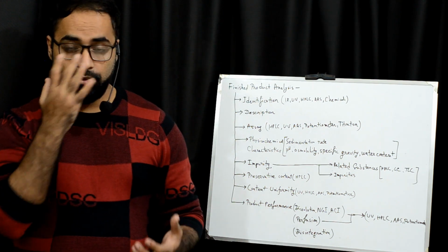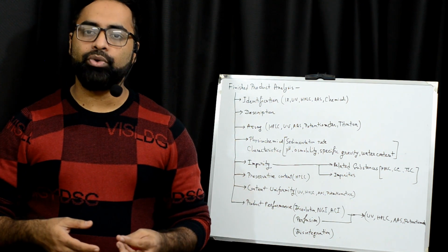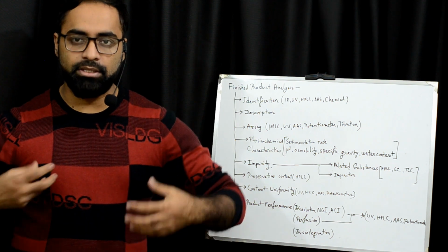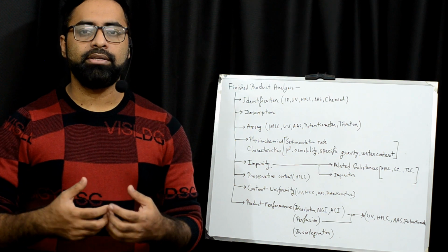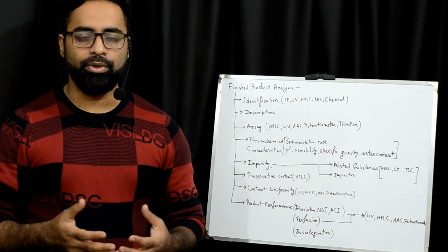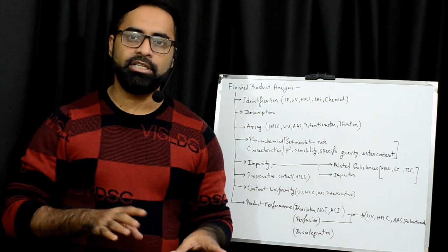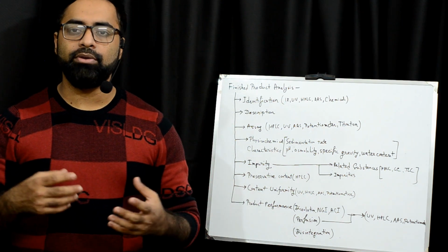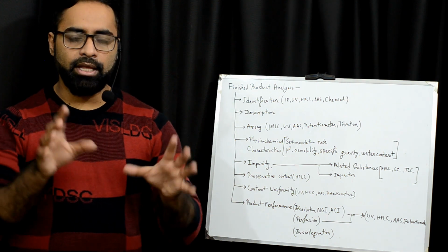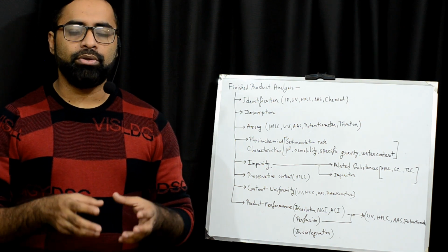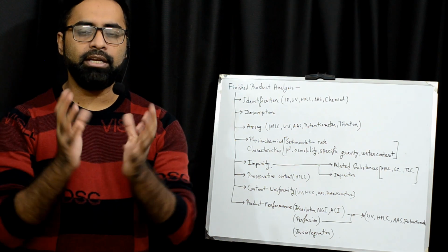In this case, we use a dissolution tester. Generally, this tester is a jacketed vessel, ensuring 37 degrees centigrade temperature. This is the temperature of the normal human body, and there are certain vessels in which there is some sort of fluid, some sort of buffer. There is a paddle or basket or any other arrangement. There are 7 arrangements in the pharmacopoeia, so we can use some arrangement like this and place that tablet or unit dose form in that vessel and test. Okay, so the test is that the tablet must disintegrate and dissolve in that fluid.